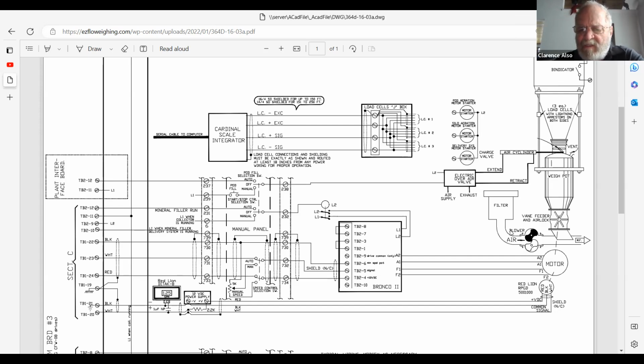This is a rotary valve here that's going to empty it. And this rotary valve here's got to have some kind of a speed control to it. And here you can see a motor going to that rotary valve. And from that point, it says okay, here's my... now this is for a DC motor right here, because it's got a field voltage and an armature voltage. And the field voltage is going to be there all the time, and the armature voltage is going to change.